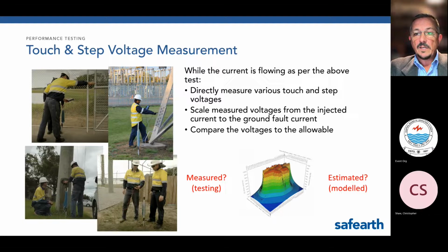This is principally because calculations can only be made of what's known about the real world, and usually to a limited extent. Testing, however, is current flowing in the real world, and all things, seen or unseen, as well. Known or unknown, all of those things affect the results in the same way they will during an actual fault. So the buried pipe, or the conductive fence, or the steel reinforcing inside the concrete footings, all of those things actually affect the performance during a test and during the real fault. And that's via conductive connections, but also inductive connections as well.